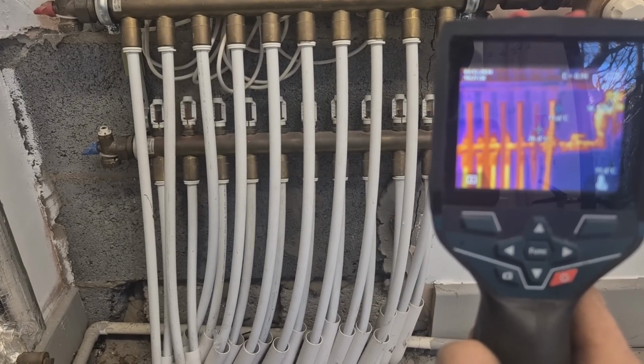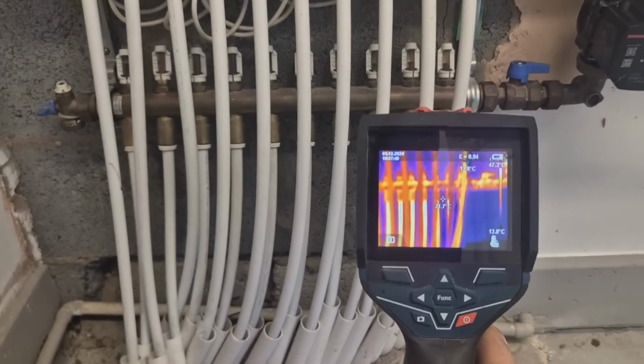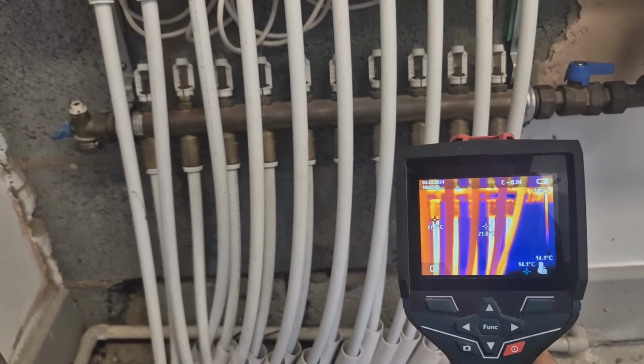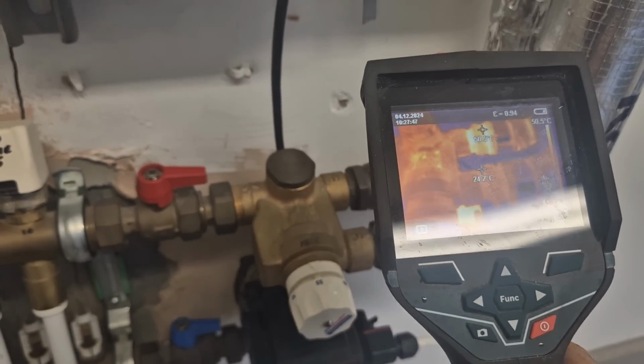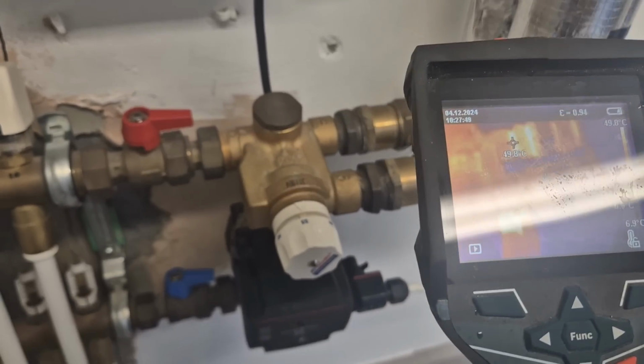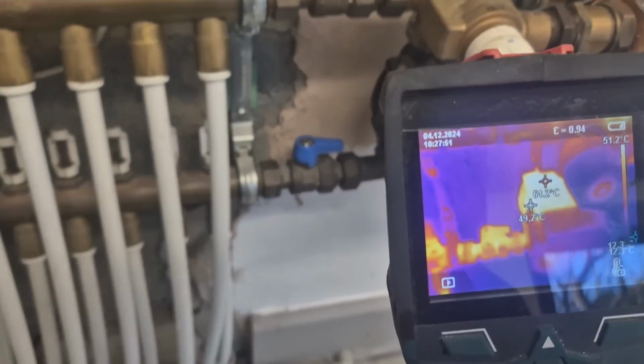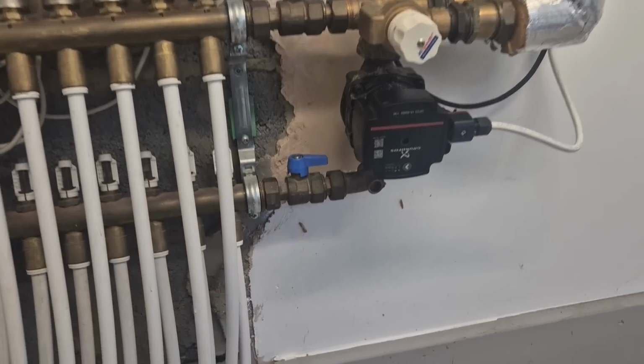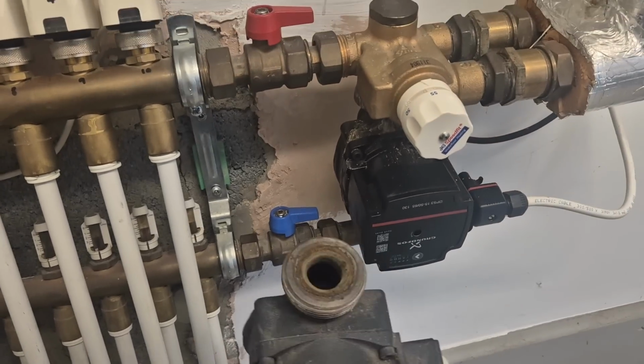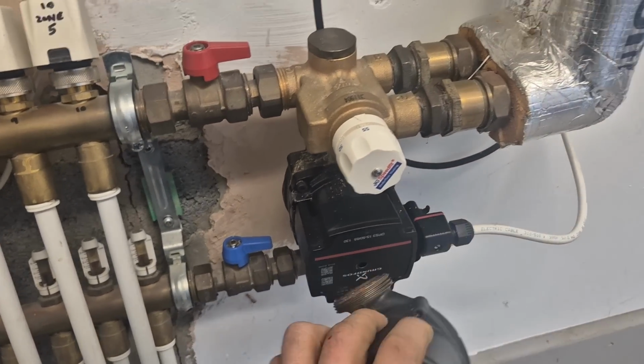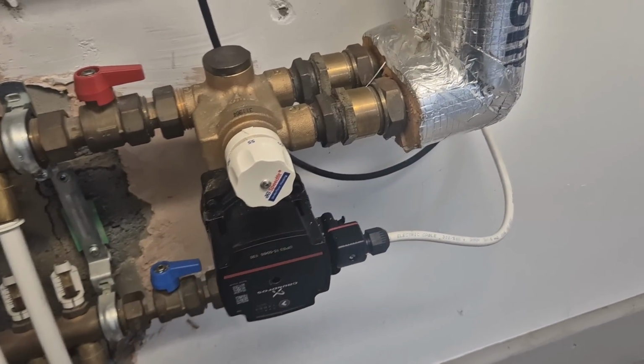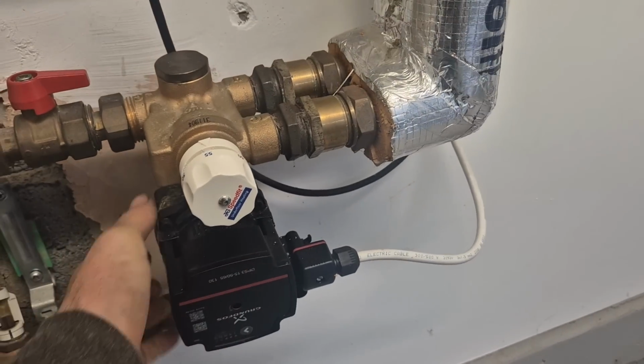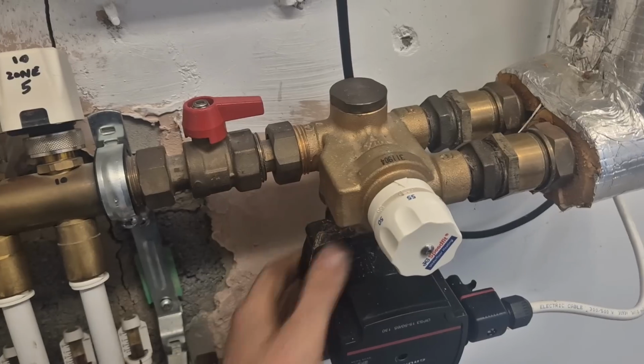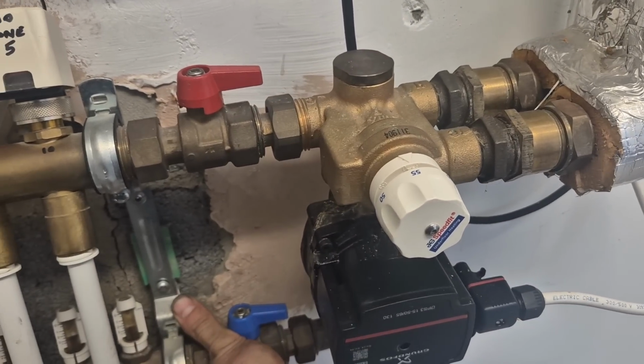That one's a bit cool, zone 4. But again, it's because it's going the wrong way around. It's going through the return. What they're doing with the pipe work here then, because that should be the flow in, it's 50 degrees, return out, and then that pump's going backwards. It's 2022, that pump. There's the old one. I would say what they've done is, because of the head, it was looking like that before, and the cable didn't reach, so instead of flicking the head around, they put the pump in the wrong way. So it means the flow gets hotter than the return.